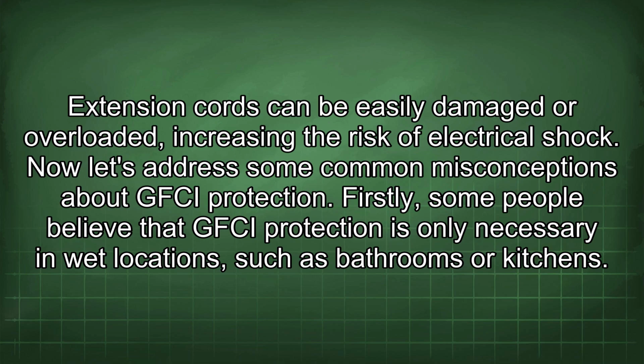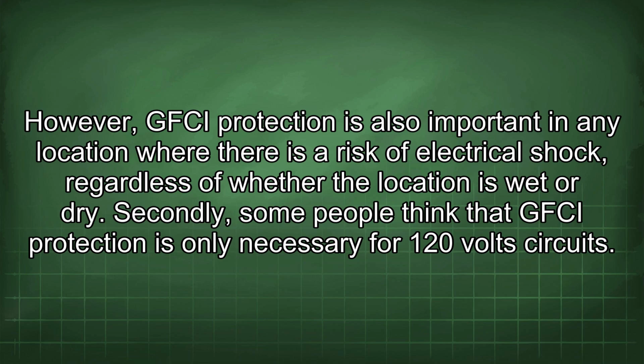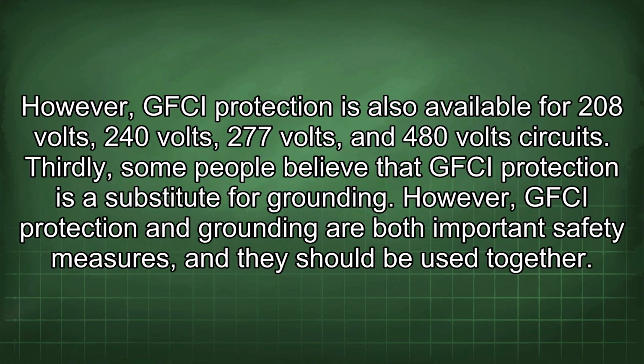Now let's address some common misconceptions about GFCI protection. Firstly, some people believe that GFCI protection is only necessary in wet locations such as bathrooms or kitchens. However, GFCI protection is also important in any location where there is a risk of electrical shock, regardless of whether the location is wet or dry. Secondly, some people think that GFCI protection is only necessary for 120-volt circuits. However, GFCI protection is also available for 208 volts, 240 volts, 277 volts, and 480-volt circuits.